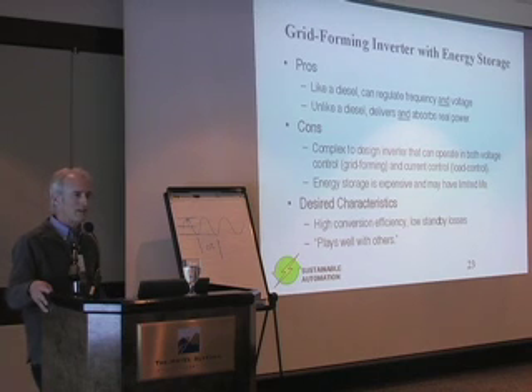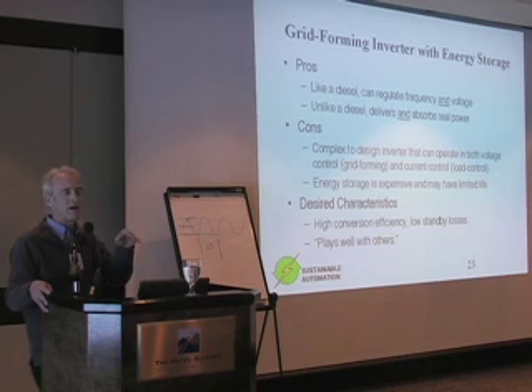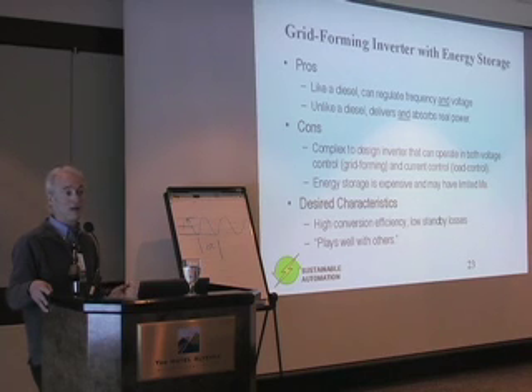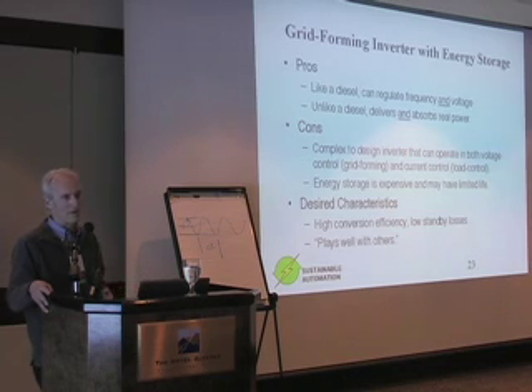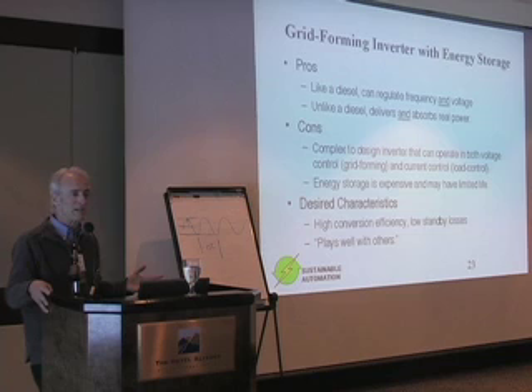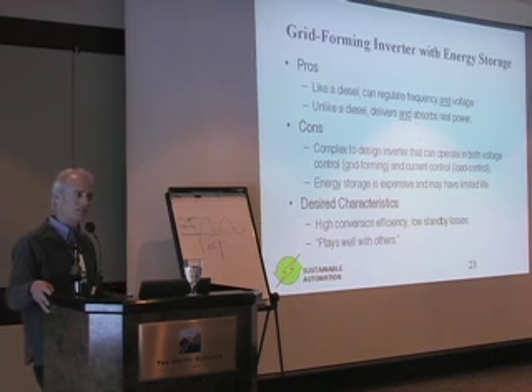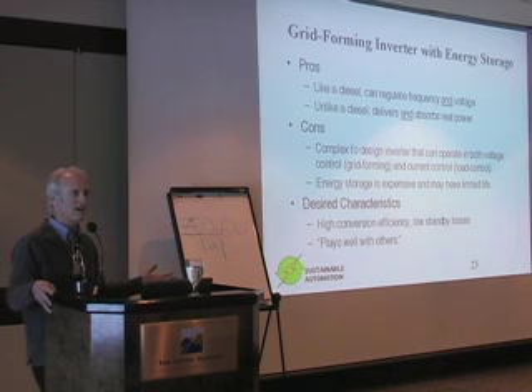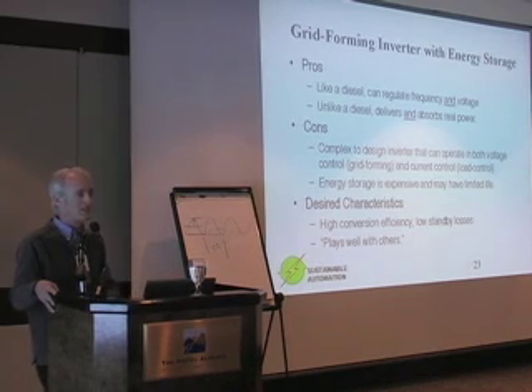Because you could spend 2 days where your average wind power is 105 kilowatts with your load, your average load being 100 kilowatts. But every few minutes, the wind might drop down to 80 kilowatts or 90 kilowatts. But no, it's only going to last for a few minutes. So if you didn't have storage in such a system, you'd have to have spinning reserve on that whole time, burning fuel because you want to run the diesel at a certain minimum load, or accumulating wear on the diesel just because it's running and it's chewing up its interval between oil changes and overhauls.